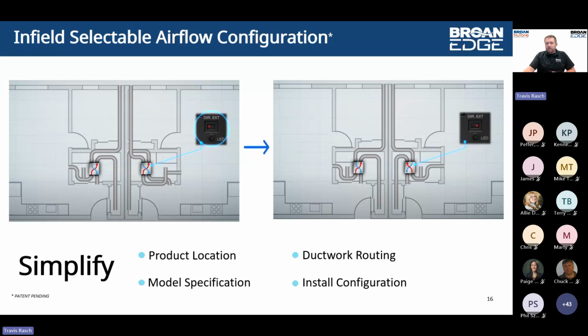Looking at the Q&A, we answered that one from Kenneth. Craig asks, can the exhaust fan or supply fan be turned off without turning off the entire unit, with only one of the fans operating? Craig, the only time that would happen currently is when we're in defrost. If the outdoor air temperature gets to a point that we've set limits for, we're going to actively turn off the supply fan during that defrost time. It's not something we can do externally; we can't turn off the exhaust or the supply independently. It's simply during that automatic defrost operation.